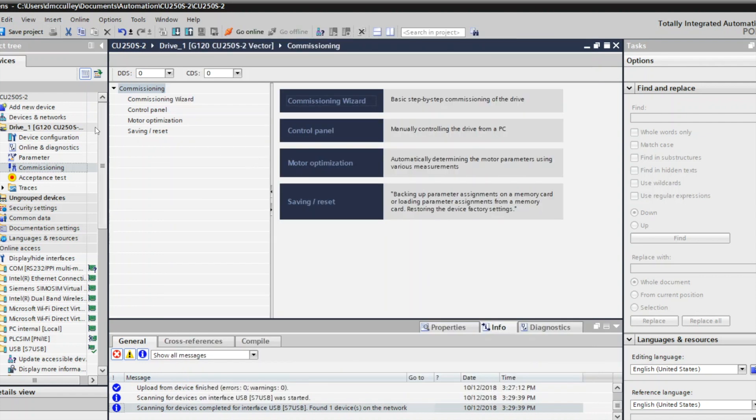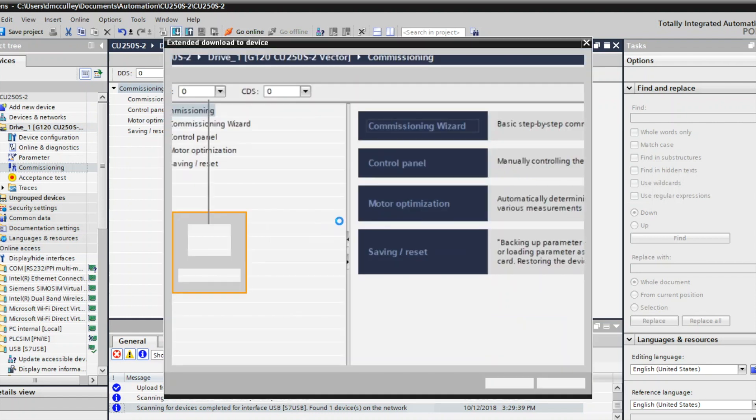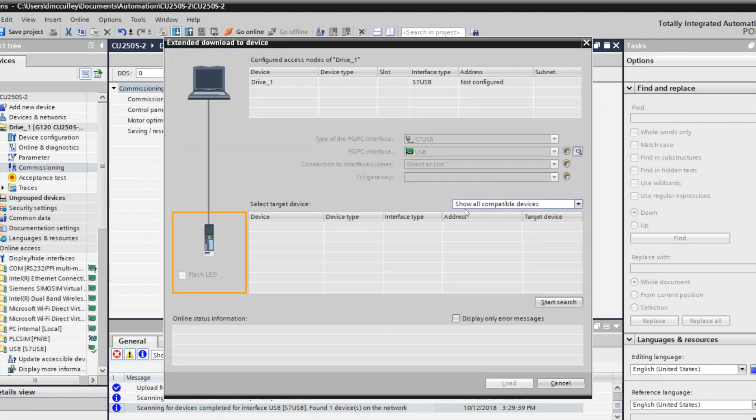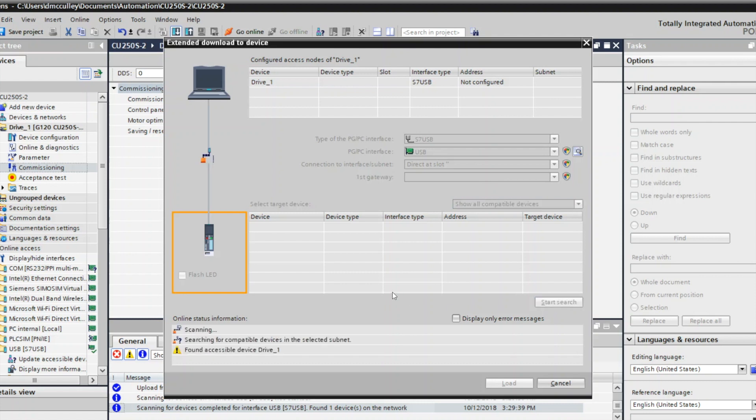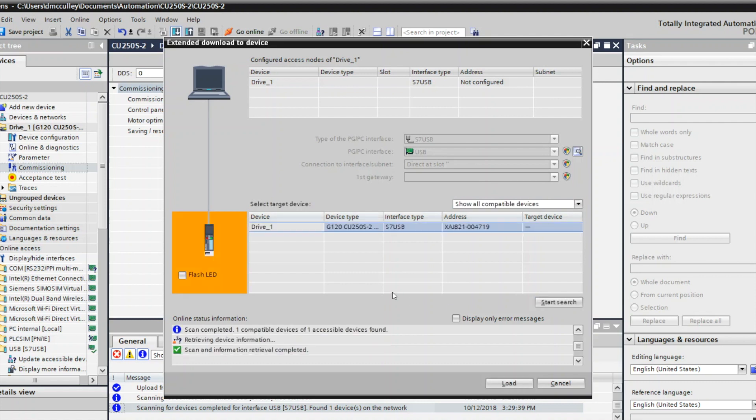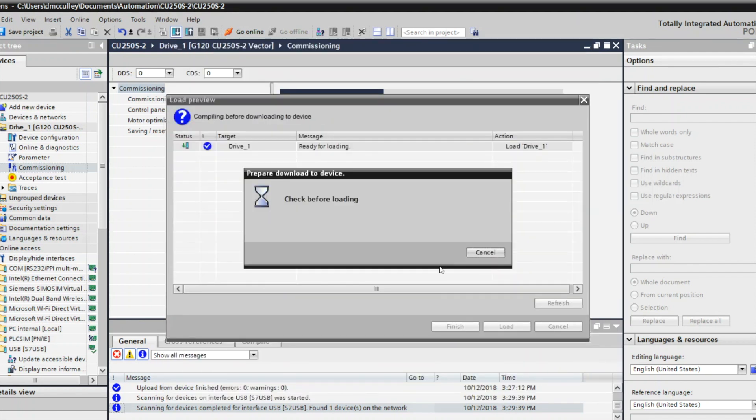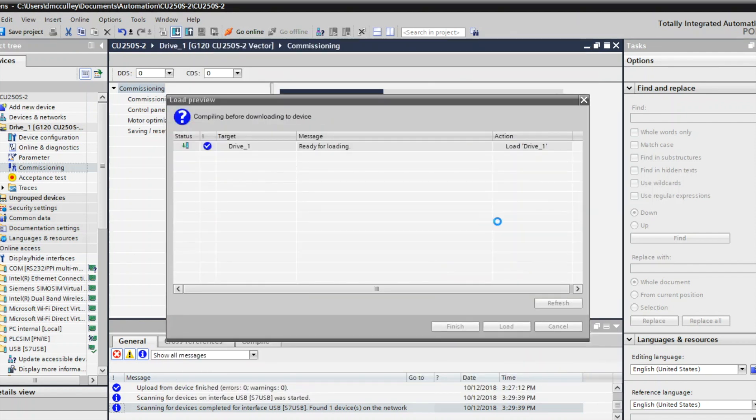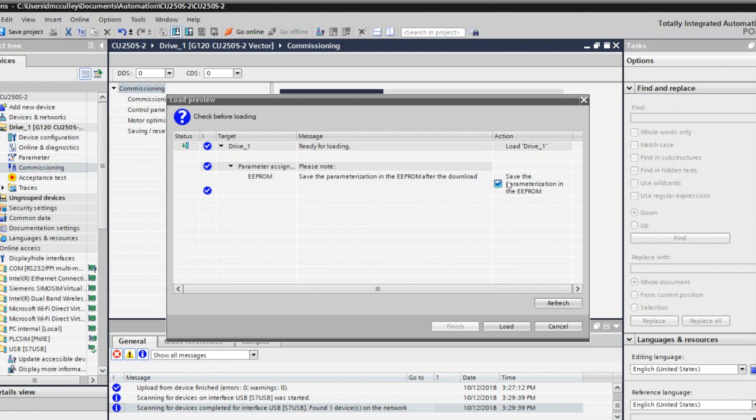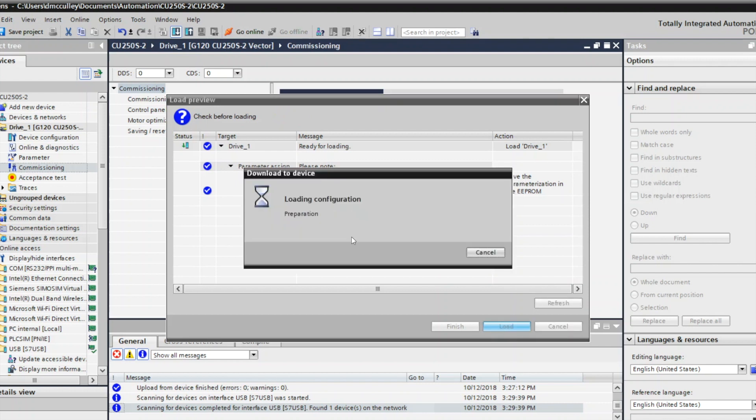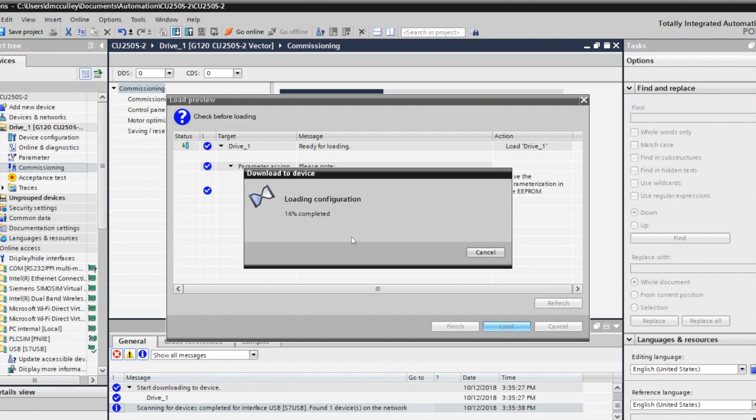Now I want to download this to the drive. I'll click the download icon. I'm connected using my USB port and the mini USB port in front of the drive. Start search. I found my drive. Now I'll load the configuration to the drive. I want to have this checked to save RAM to ROM. I'll click load, and it takes a little bit for it to load to the drive over the USB port. It seems a little bit slower, but be patient.